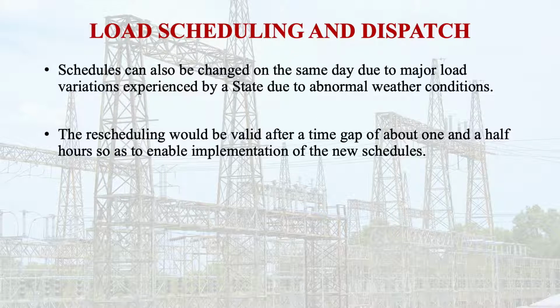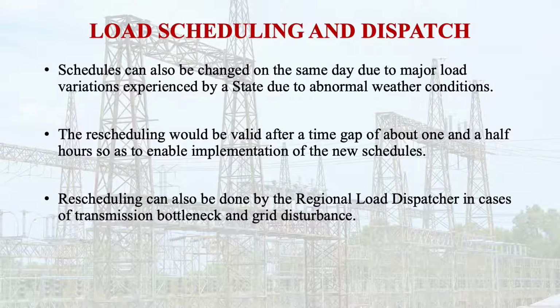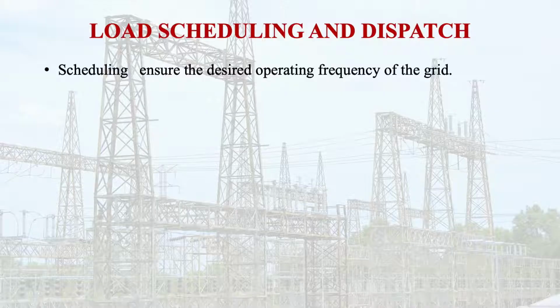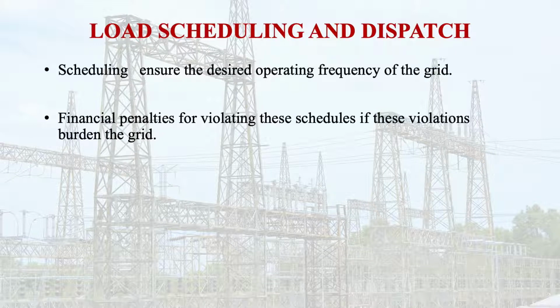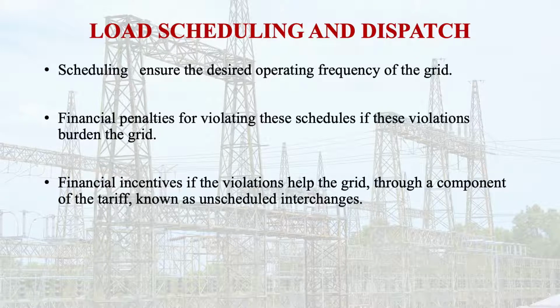The rescheduling would be valid after a time gap of about an hour and a half, so as to enable the implementation of the new schedules. This rescheduling can also be done by the regional load dispatcher in case of transmission bottleneck and grid disturbances. The state sends its required schedule to the regional load dispatch centers. This scheduling is important because it is meant to ensure the desired operating frequency of the grid. There are financial penalties for violating these schedules if the violations burden the grid, and financial incentives if violations help the grid, through a component of the tariff known as unscheduled interchanges.